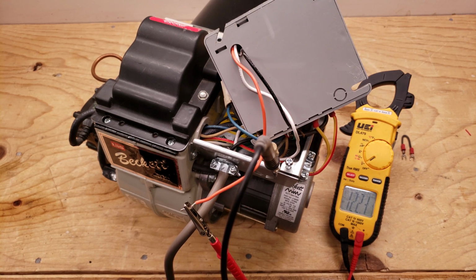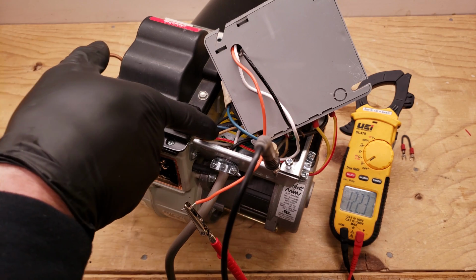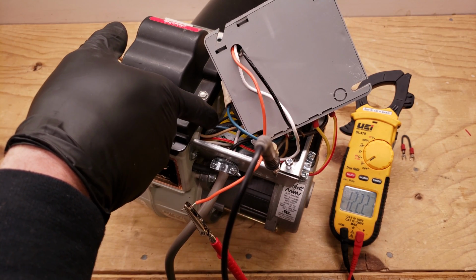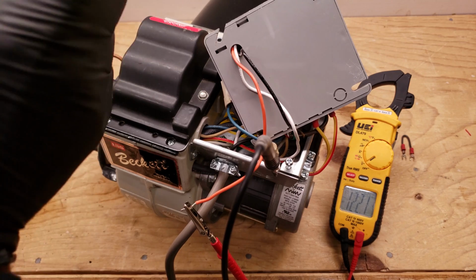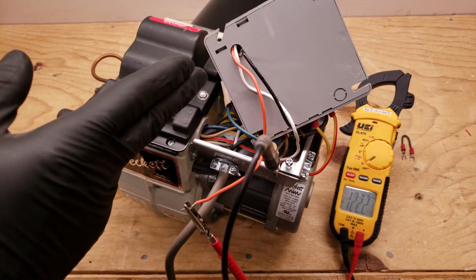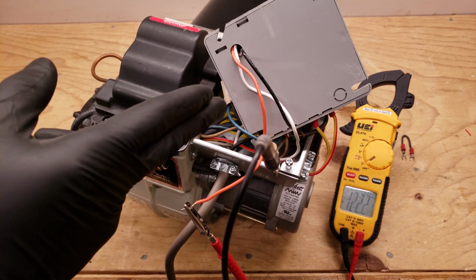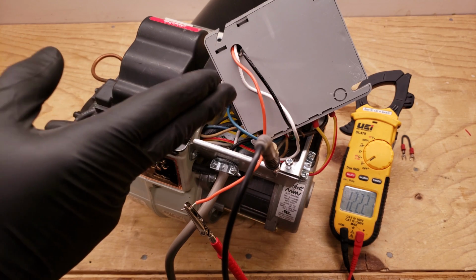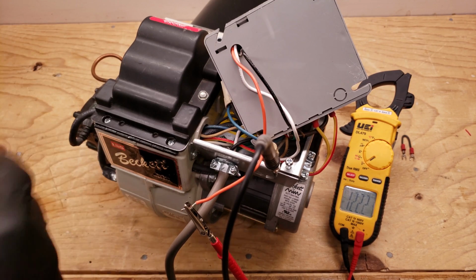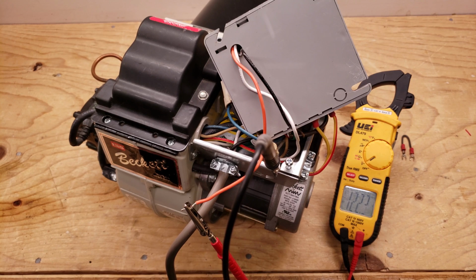And you see that we're reading 122 volts. Now, you also may have a problem just due to light right in here, maybe getting to the CAD cell and not allowing the primary control to turn on. If that's the case, what you can do is you can just disconnect your wires to the CAD cell at the F and F terminals while you're doing this test. But right now you see that it's reading 122 volts. So that oil primary control is good.